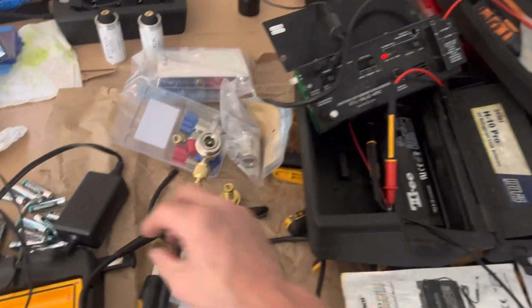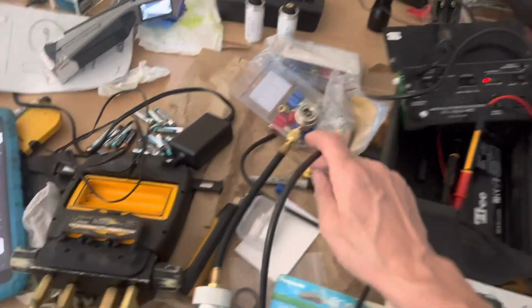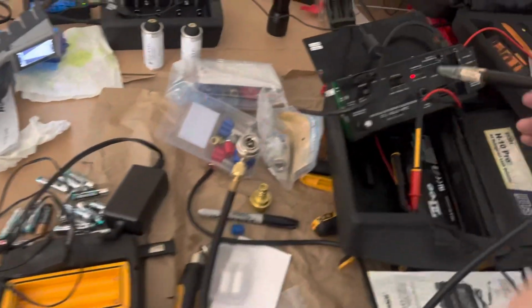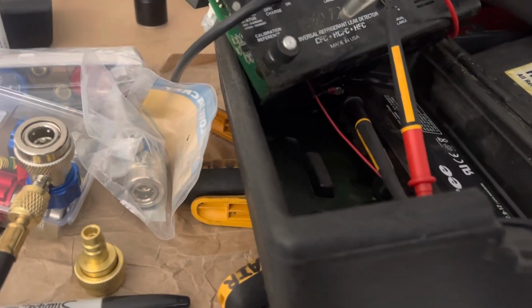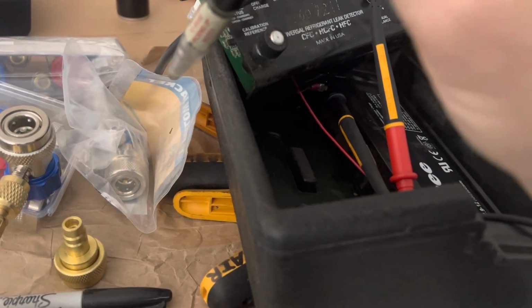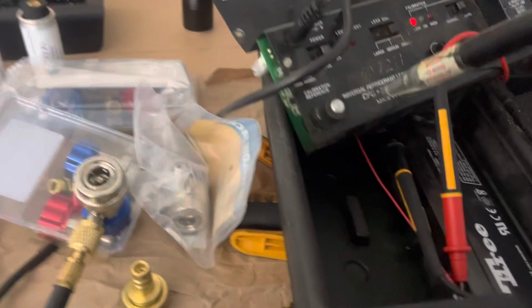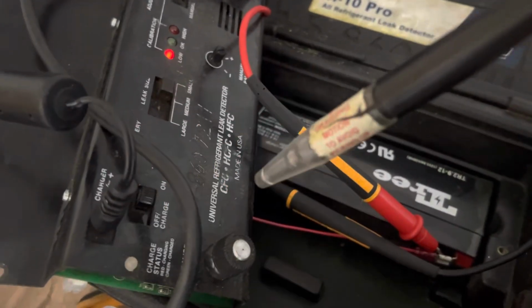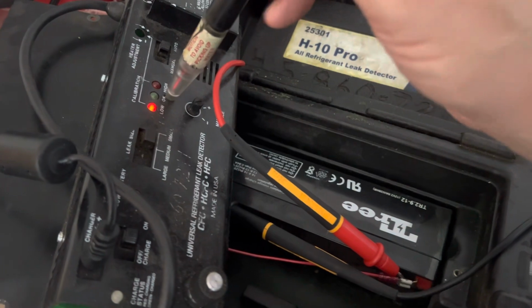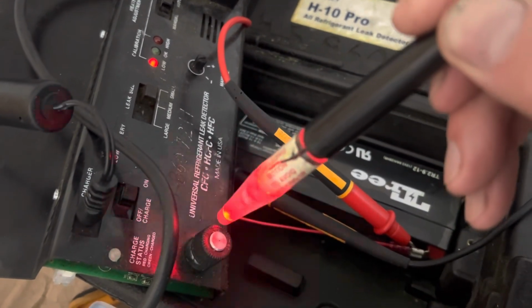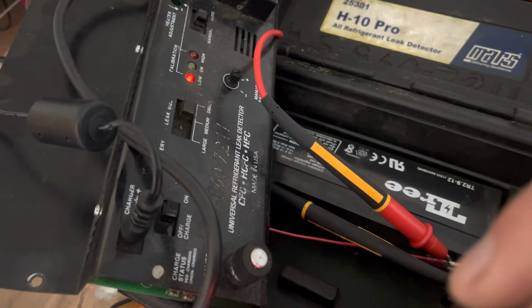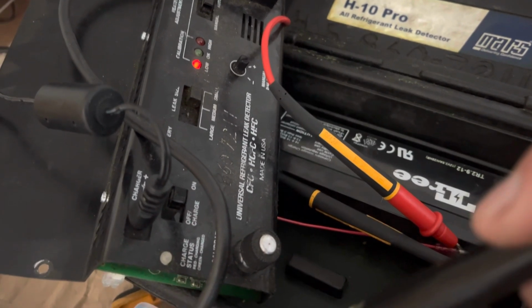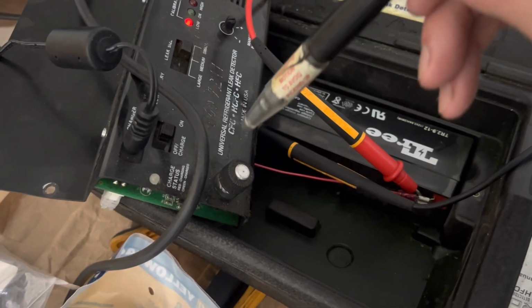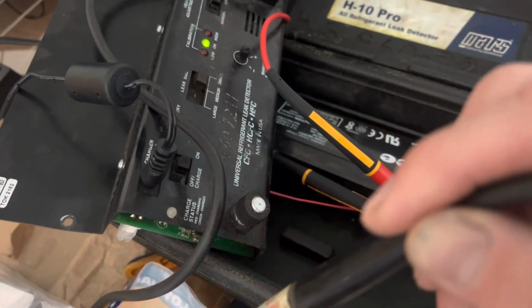So right here, I just finished a calibration, and I don't need to show you all the details, but you can see when you take your leak detector, you will pass it just over the surface of the hole without stopping and without touching, like that. So you stay up, say 3/8 of an inch, 1/4 inch. Now you'll see this red light right here go into the green as I go over it. Did you see that? And did you see how far away I was? I did not touch it, and I did not stop over it. It was just a pass over. That's how sensitive this is.